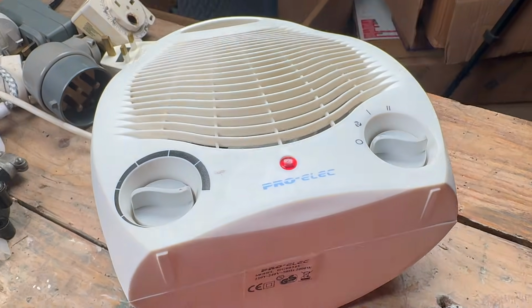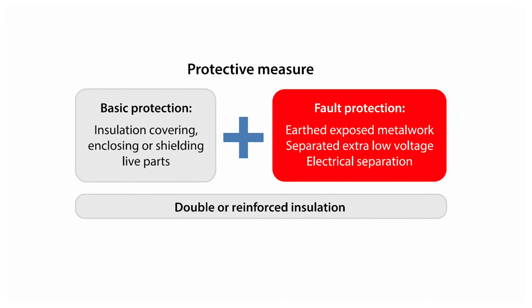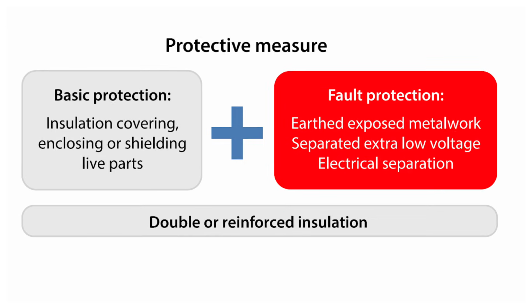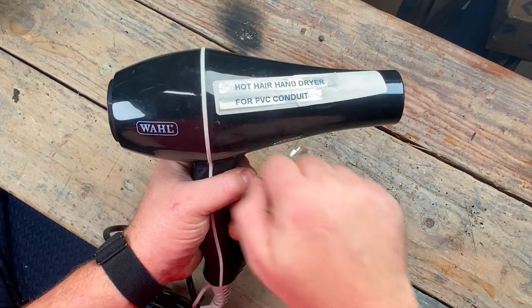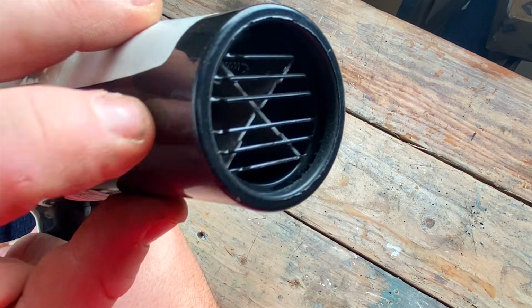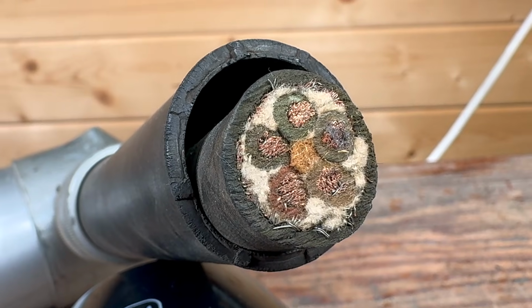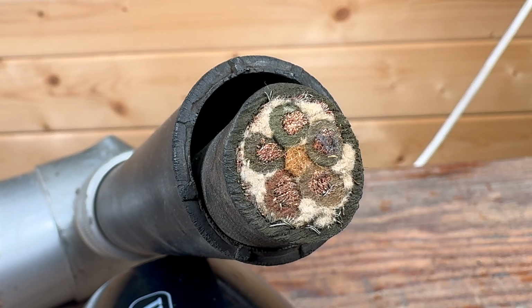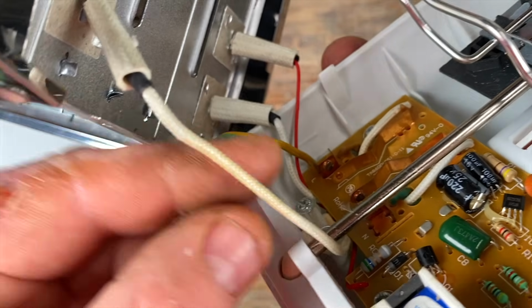Okay, so now let's get into classifications, because if we can't understand how the equipment protects the user, then we can't test it correctly. Every item of electrical equipment has one purpose when it comes to user safety: prevent electric shock. To do that, it relies on two layers of protection. The first is basic protection. This prevents accidental contact with live parts during normal use. The most familiar example is insulation around conductors, but inside equipment this could also be insulating barriers.